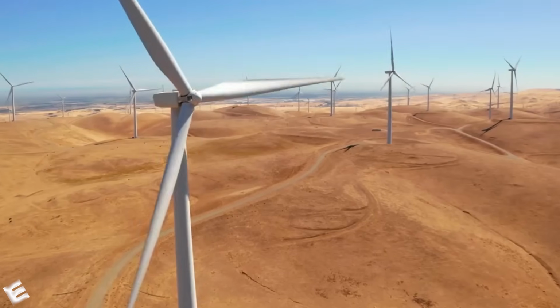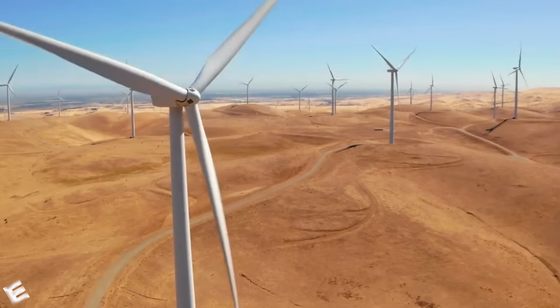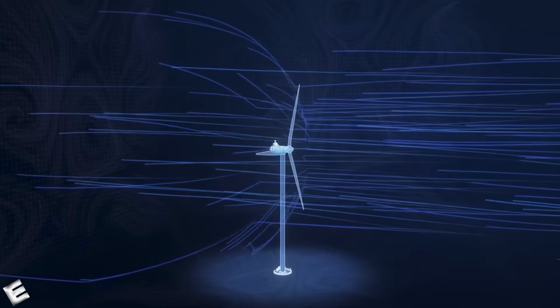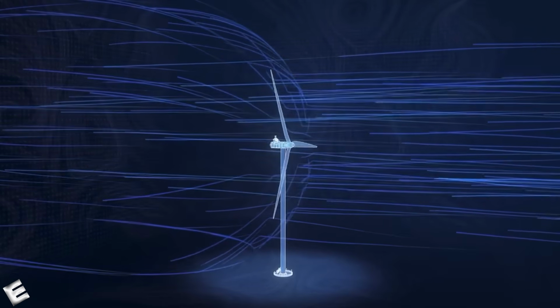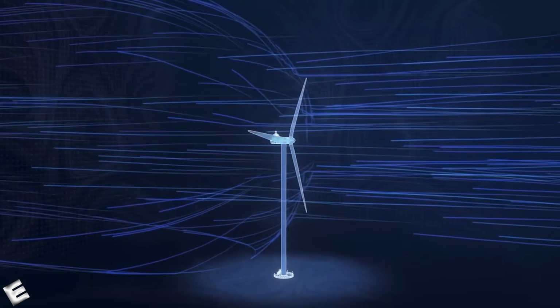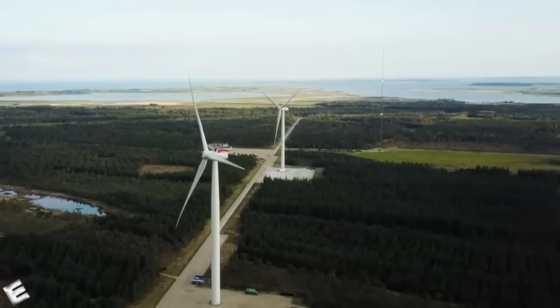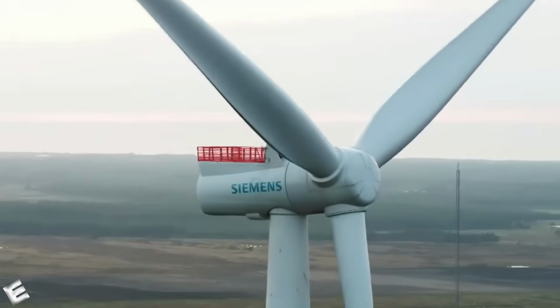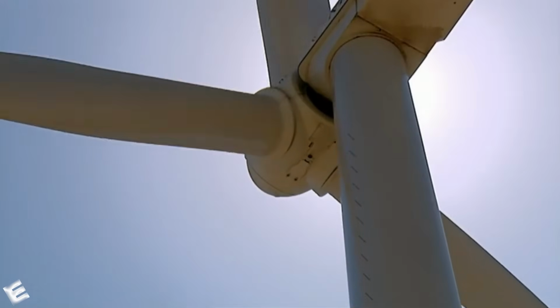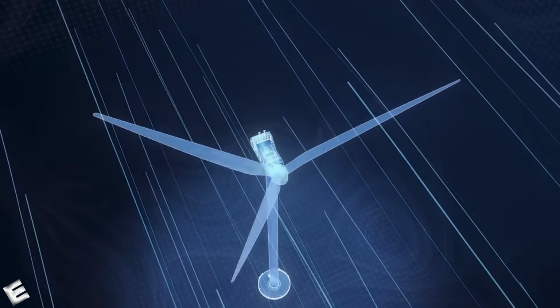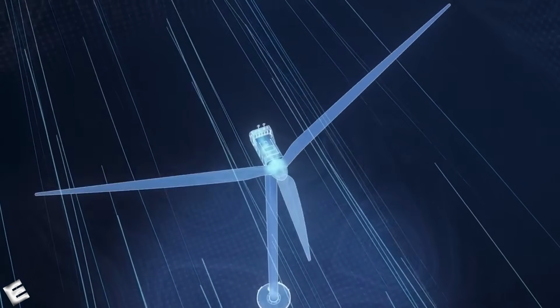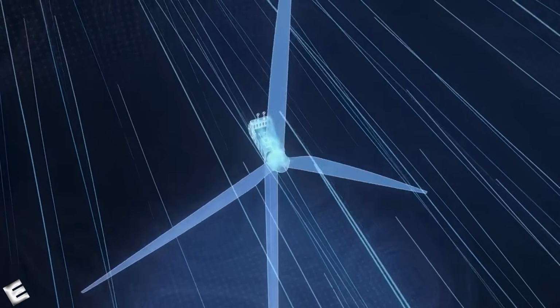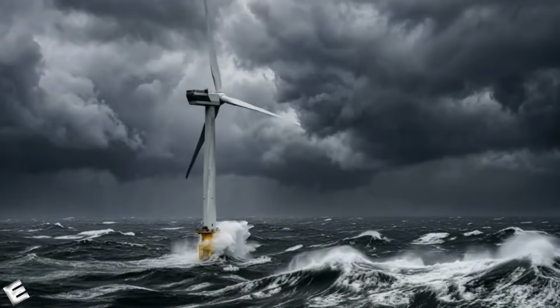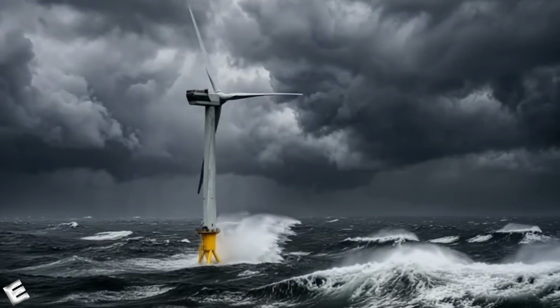Because even though it may sound contradictory, too much wind can also be a problem. A wind turbine does not operate endlessly at any wind speed. Normally, it begins producing electricity when the wind reaches between 6 and 9 miles per hour. Its performance then increases progressively until it reaches maximum power, usually between 28 and 34 miles per hour. But if the wind exceeds speeds close to 56 miles per hour, the safety systems activate and completely stop the machine to protect it.